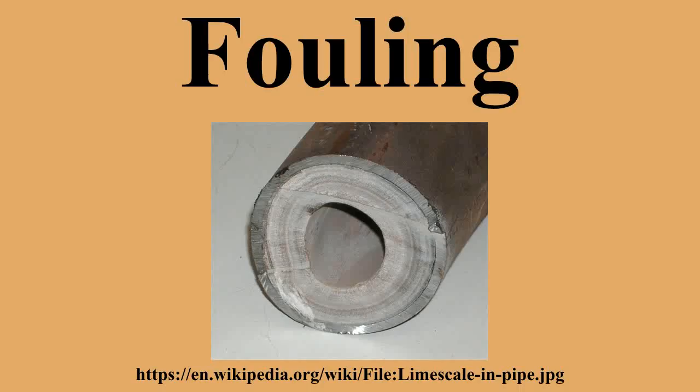can also be affected. The ingress of macrofouling into the cooling tower basin is possible through open canals or by the wind. Sometimes parts of the cooling tower internals detach themselves and are carried into the cooling water circuit. Such substances can foul the surfaces of heat exchangers and may cause deterioration of the relevant heat transfer coefficient.